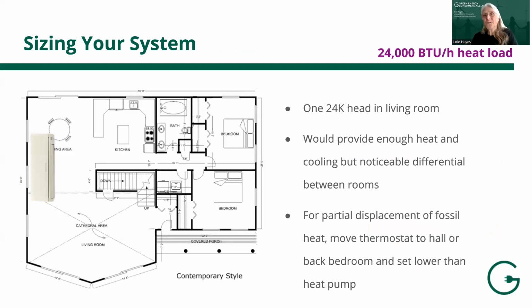So let's look specifically at sizing your system, because one thing we want to warn you against is oversizing. This has been one of the major concerns that we've seen come up in people who've installed so far. I'm going to show you 3 slides with this same illustration of a home. This is a 2-bedroom home, and we have posited that the heat load, the amount of heat that's needed to keep the home warm on the coldest night of the winter, is 24,000 BTUs of heat per hour. A BTU is a British thermal unit. So 24,000. And in this illustration, we've put a 24,000 BTU head in the living room, dining room, kitchen area. And that would provide enough to keep the whole house from freezing.